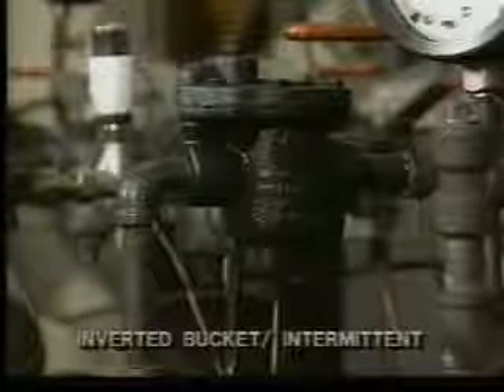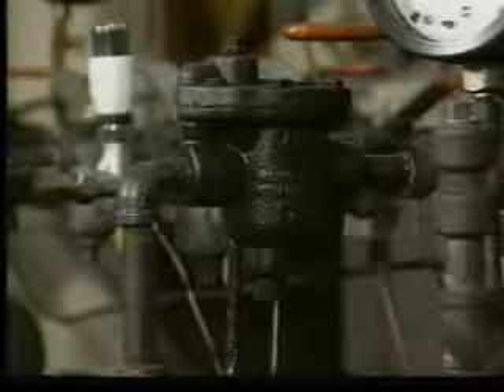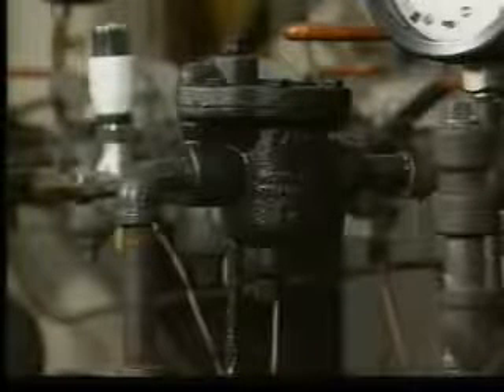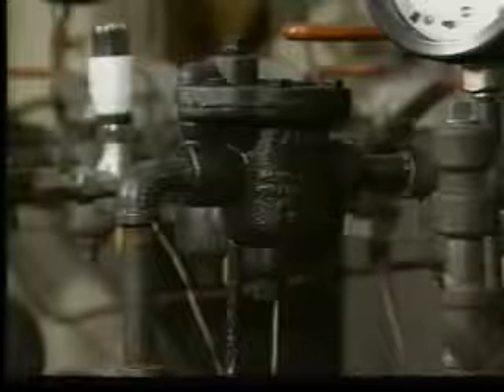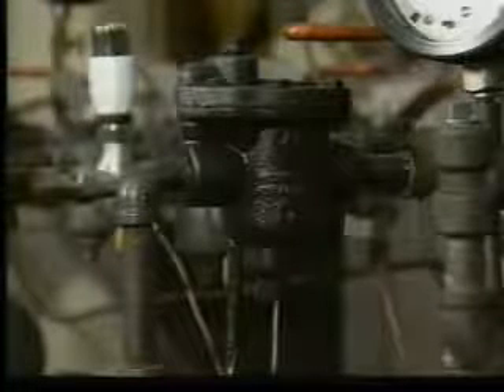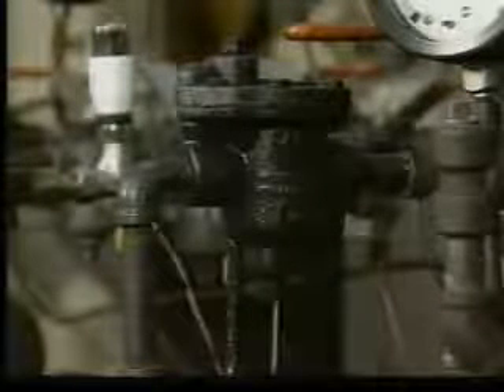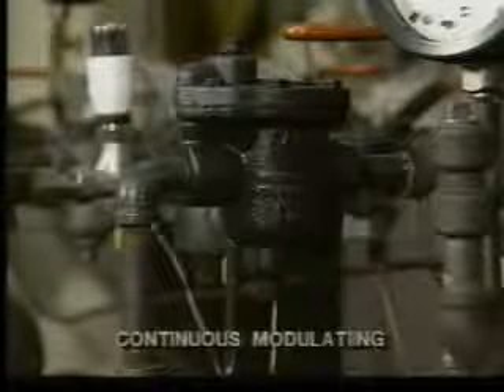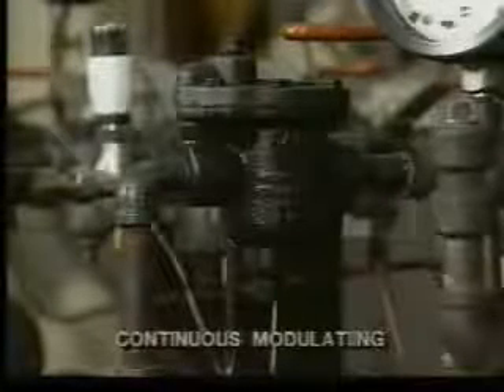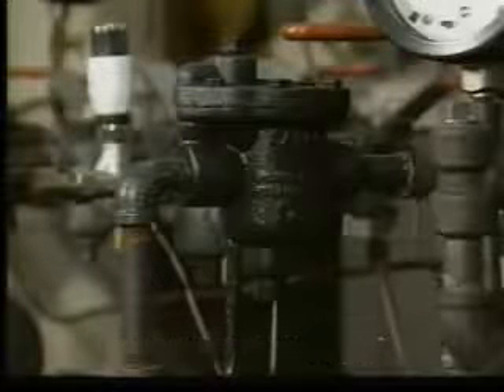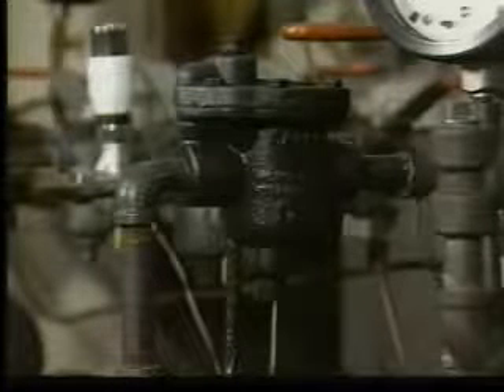The inverted bucket, or IB trap, is an intermittent trap, and it makes a definite opening and closing sound. Sometimes the IB trap may experience continuous modulating or dribbling, especially with light loads. This may sound like a continuous flow, but it's just the normal, very rapid opening and closing of the main orifice valve.